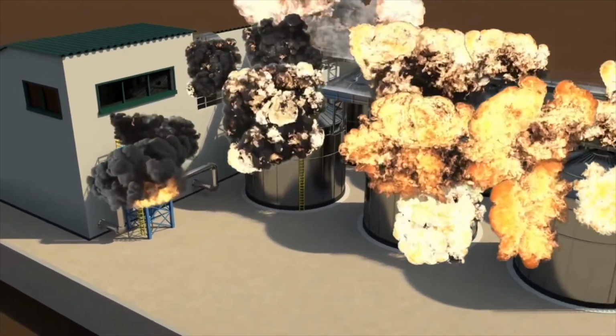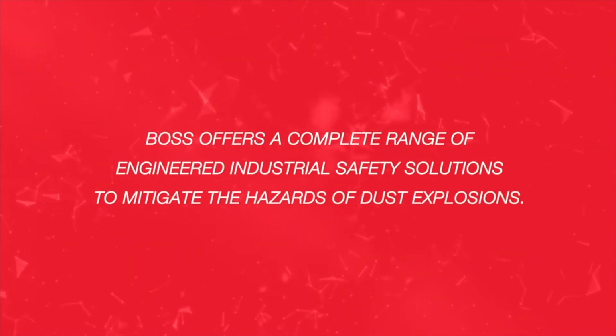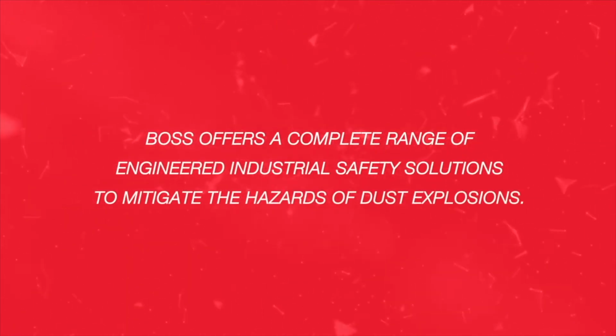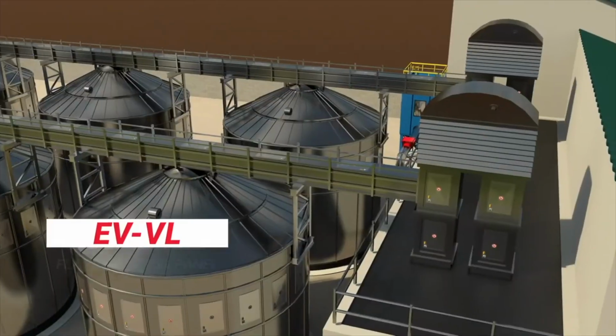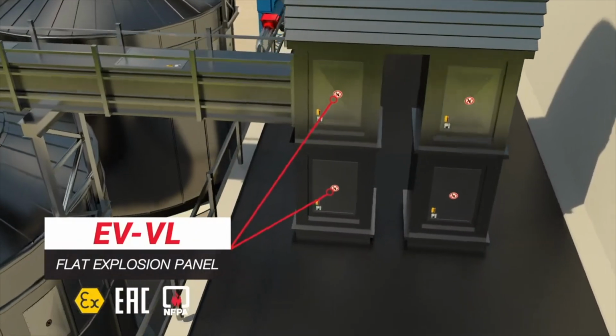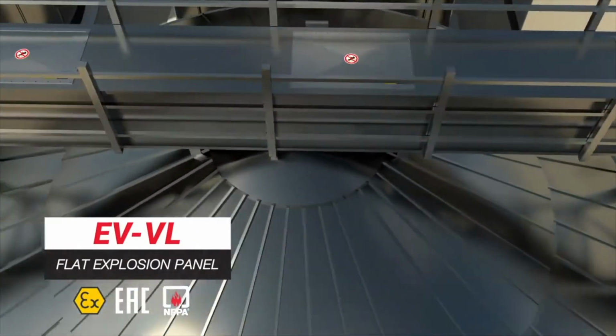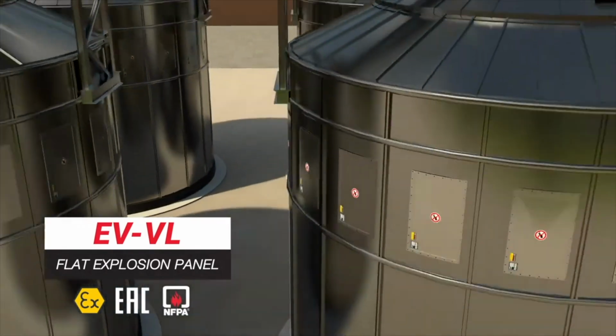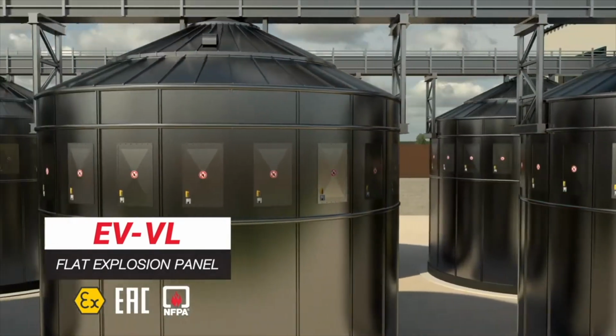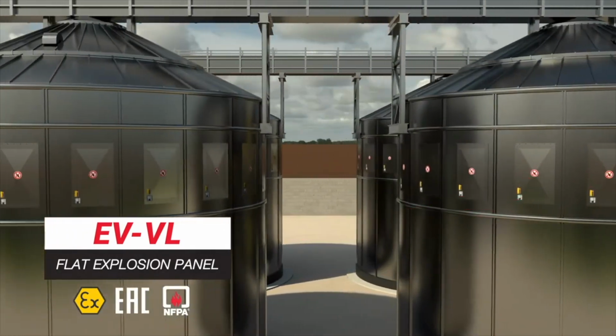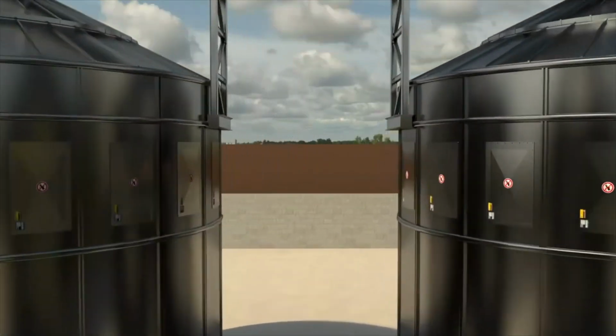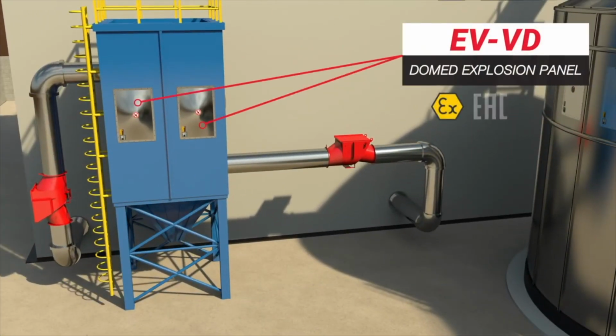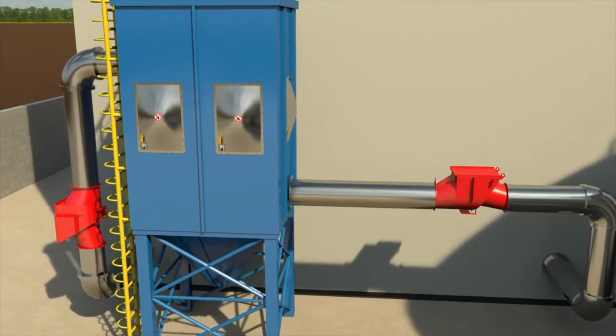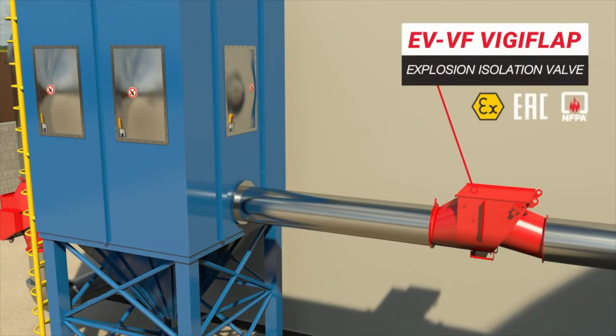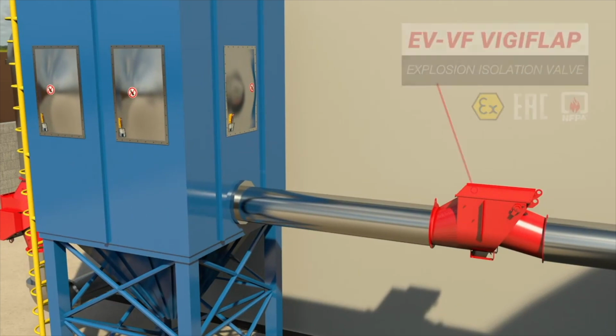What we can do is, if your collector is also outdoors, we can just put standard vents on there, and we also do offer vent deflectors, which are basically, if you have property or people nearby, you can put this vent deflector panel on the explosion relief panel, and in the event of the explosion, the vent panel folds over, relieves the pressure, and the fireball shoots up and out, so it doesn't cause any injury to any nearby personnel. We offer different types of explosion vents, flat panels, dome panels. We also offer round panels and high vacuum panels for high vacuum systems.